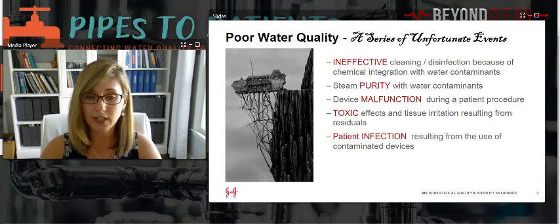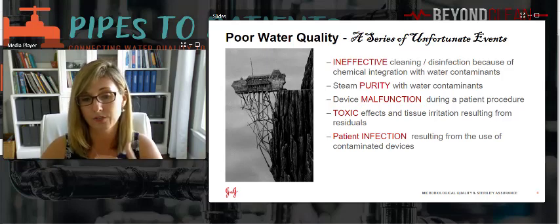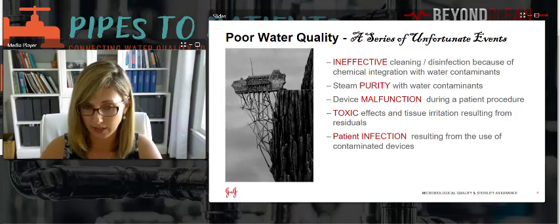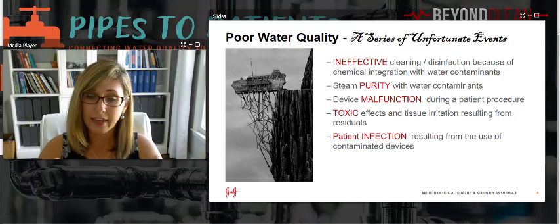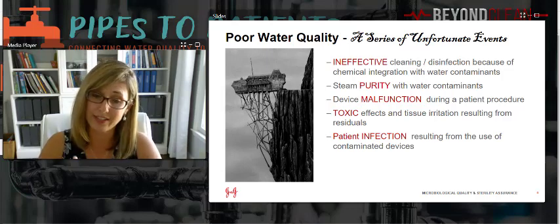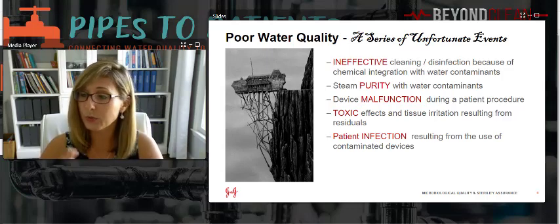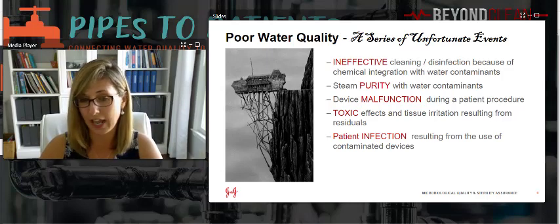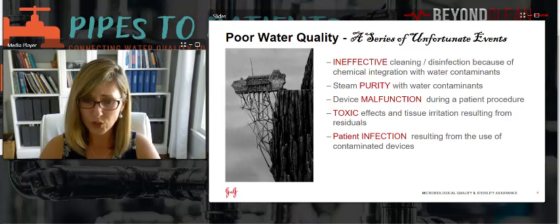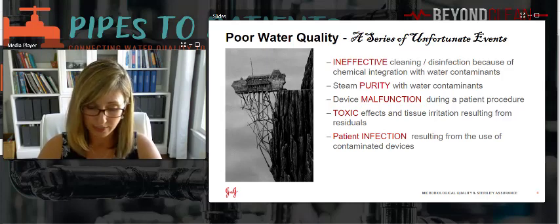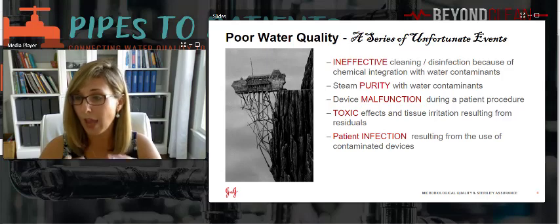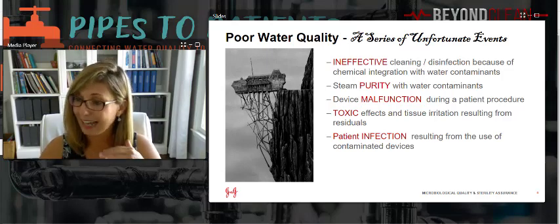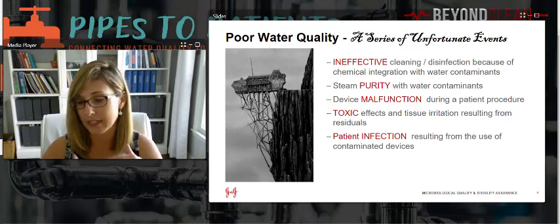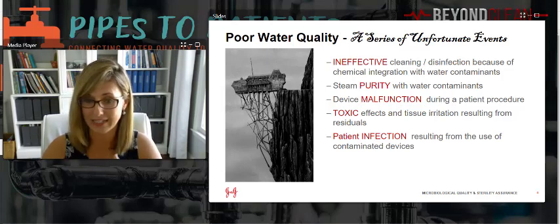And then the final one is really that idea of patient infection. So salt or organic deposits used in the processing of medical devices can inactivate the ability for the disinfectant or sterilant to really inactivate any microorganisms that are on the device after use. So it's really important that we don't provide a way that bugs can hide and not be able to get sterilized or disinfected as we intended.